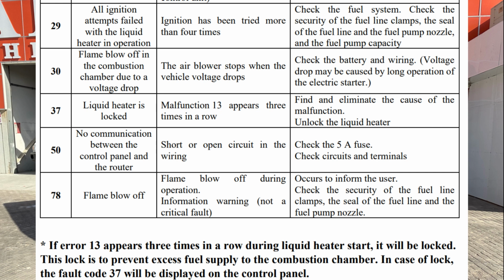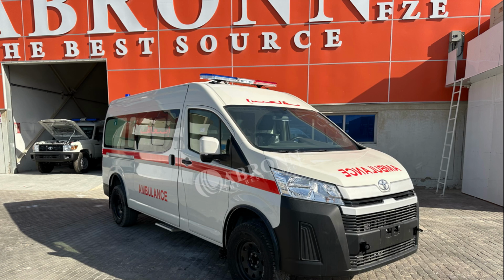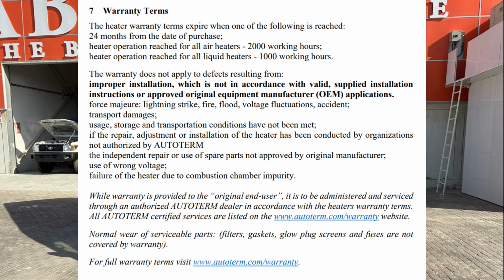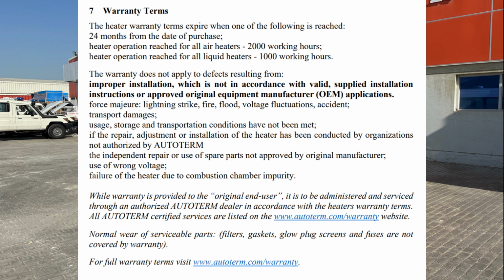For diesel heaters, if a separate fuel tank is used, fuel in the system has to be changed at least once a season. Before the start of the heating season, check the fuel tank. If the tank stored fuel for a long time, for example from the past heating season, it is necessary to drain it. Rinse the tank with gasoline or kerosene and fill it with fresh diesel fuel. This procedure is designed to remove sediment formed in the fuel during prolonged storage.